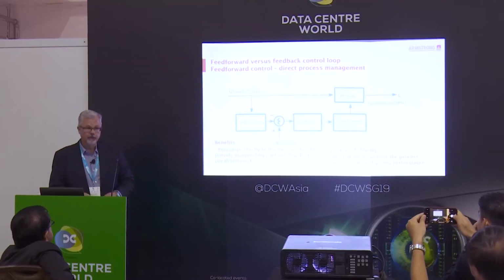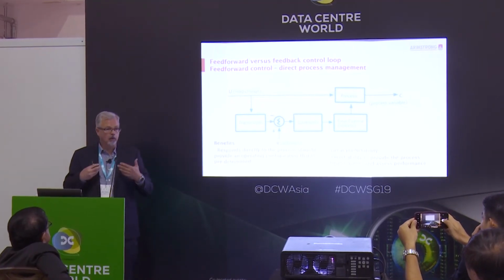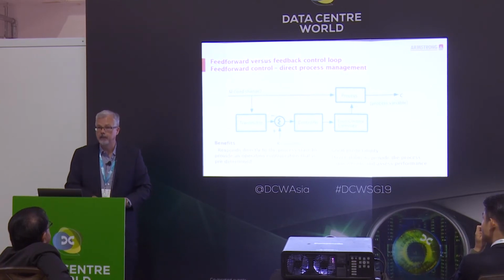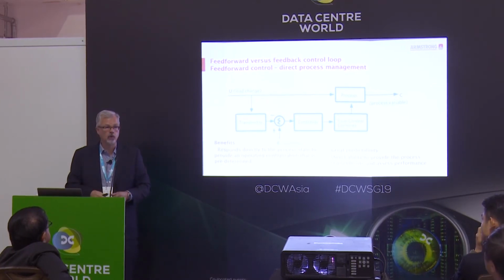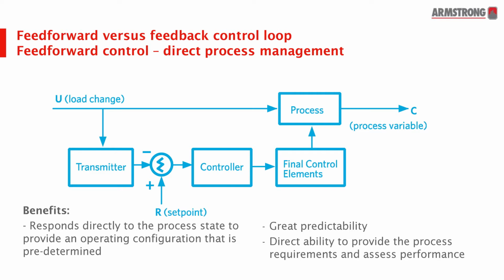So let's talk about feed-forward control. This is the more important thing to understand, and if we employed feed-forward control in this space, we would be able to count the number of people, know that for your size and your weight, how many calories of heat energy you're releasing into the space, how many lights are in the space and how much power those lights are putting into the space, and all the other sources of heat. We'd say we need to apply 200 kilowatts of cooling to that space.